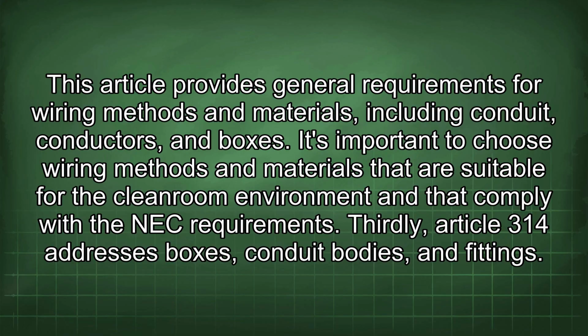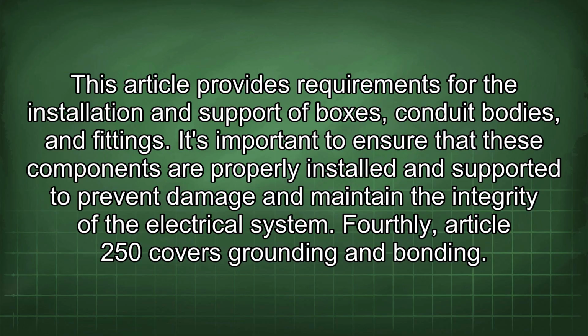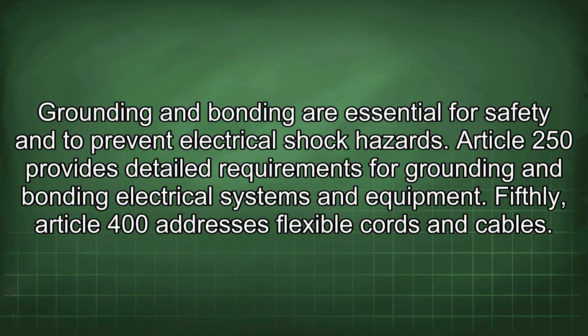It's important to choose wiring methods and materials that are suitable for the cleanroom environment and that comply with the NEC requirements. Thirdly, Article 314 addresses boxes, conduit bodies, and fittings. This article provides requirements for the installation and support of boxes, conduit bodies, and fittings. It's important to ensure that these components are properly installed and supported to prevent damage and maintain the integrity of the electrical system. Fourthly, Article 250 covers grounding and bonding. Grounding and bonding are essential for safety and to prevent electrical shock hazards. Article 250 provides detailed requirements for grounding and bonding electrical systems and equipment.